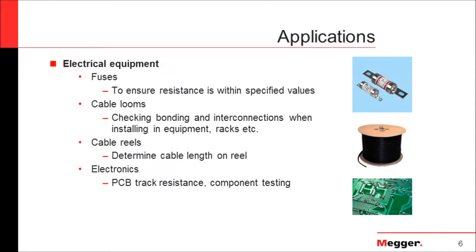Take a pretty easy example: if we have a reel of insulated copper wire, it may have a tag indicating the wire gauge and the resistance per unit of length. Or if the tag has been removed, we can just cut a small piece of cable, measure its resistance, and then when we measure the whole coil, we have a factor to calculate the total length of the wire on that drum.